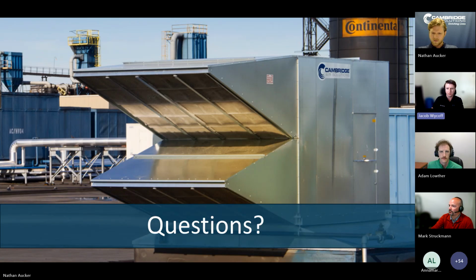His question was, can we prove that if we put the unit outside on the pad, instead of putting it up on the roof, we will have less vibration and noise into the building? And that's a good point, Ali. So while there are ways to mitigate vibration and noise for roof-mounted equipment, that can sometimes get complicated and expensive. Putting it on the pad is a great way to avoid that vibration and noise going into the building.